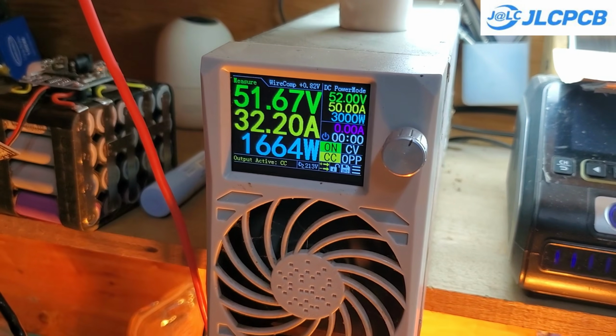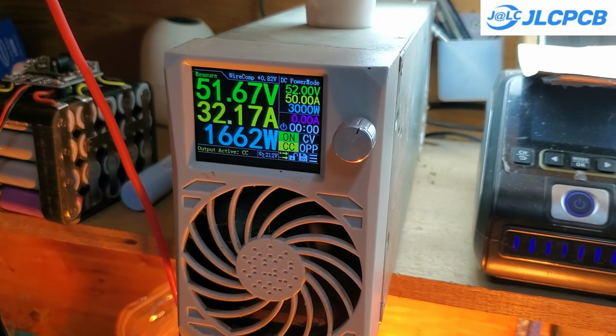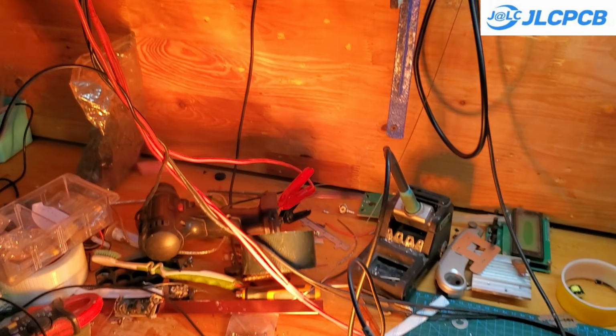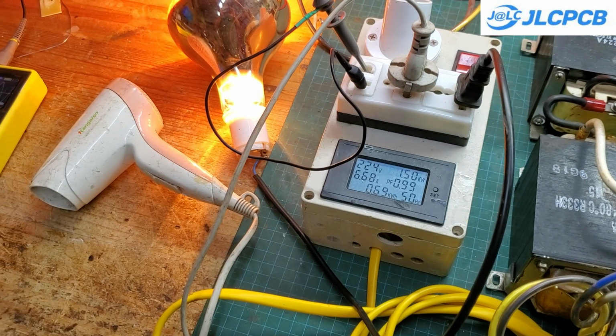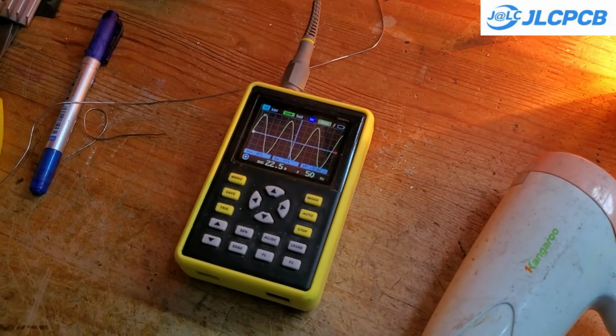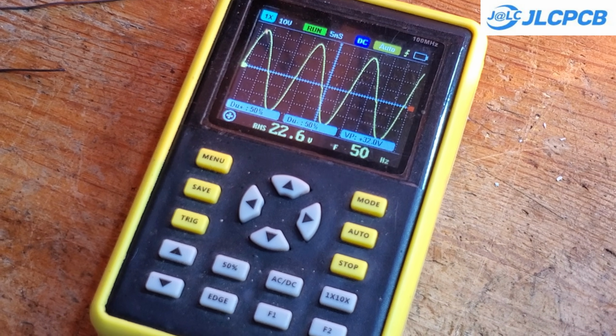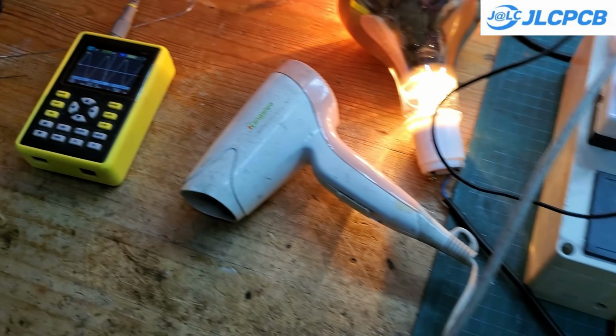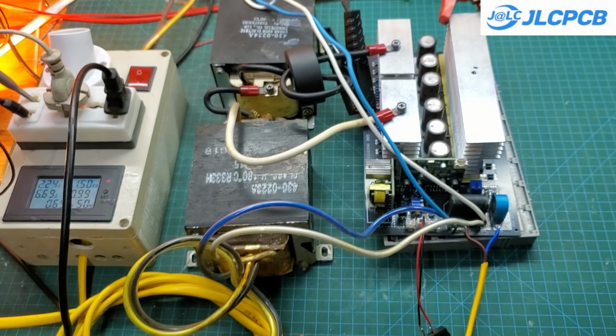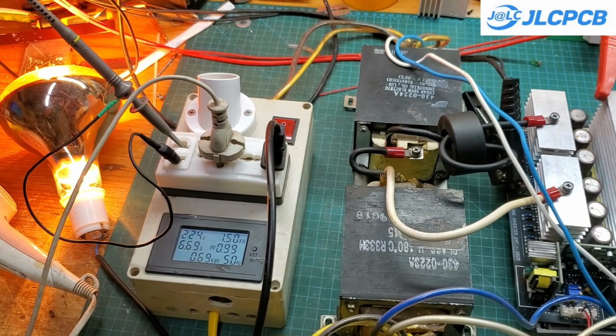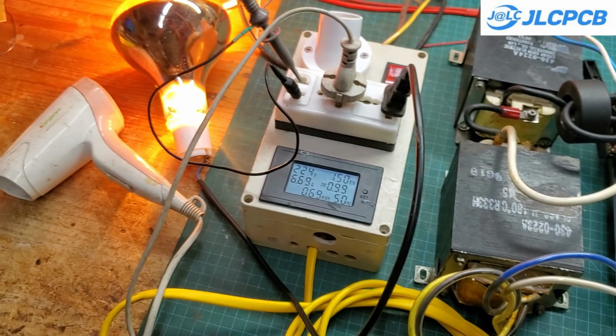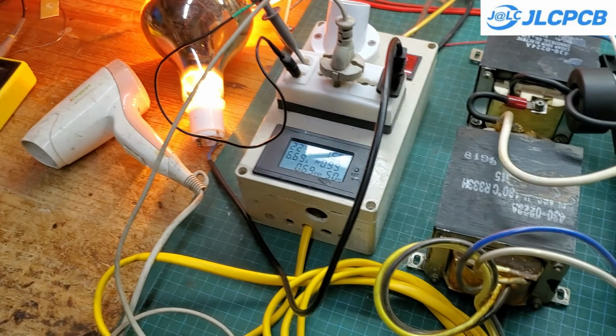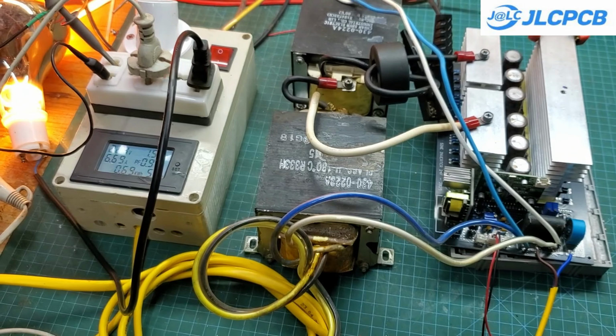The conclusion is that we can absolutely reuse a UPS transformer to build a pure sine wave inverter. The downside is that the overall efficiency would be about 1 to 2% lower compared to a toroidal transformer. I'll inform my customer so they can choose between a 24-volt or 48-volt system, and then I'll assemble everything into a new enclosure. In the end, the profit from this job is around $50.